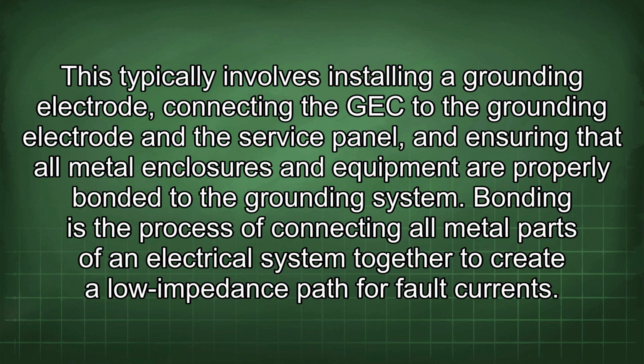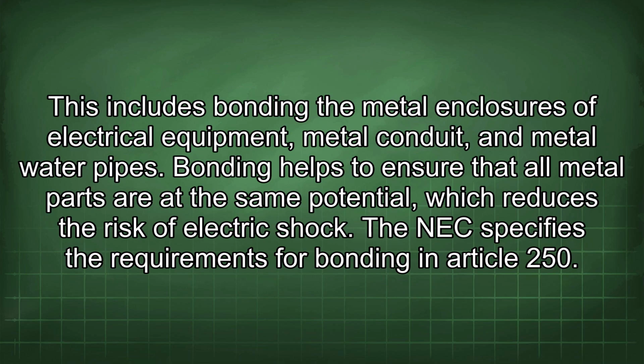This typically involves installing a grounding electrode, connecting the GEC to the grounding electrode and the service panel, and ensuring that all metal enclosures and equipment are properly bonded to the grounding system. Bonding is the process of connecting all metal parts of an electrical system together to create a low impedance path for fault currents. This includes bonding the metal enclosures of electrical equipment, metal conduit, and metal water pipes. Bonding helps to ensure that all metal parts are at the same potential, which reduces the risk of electric shock.